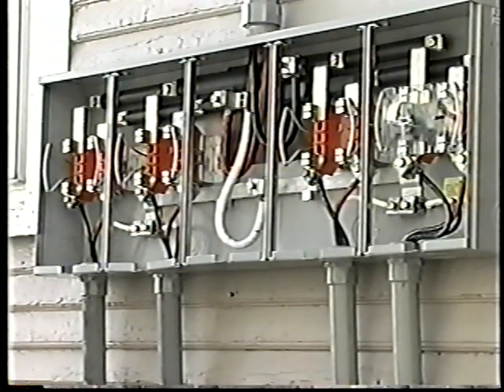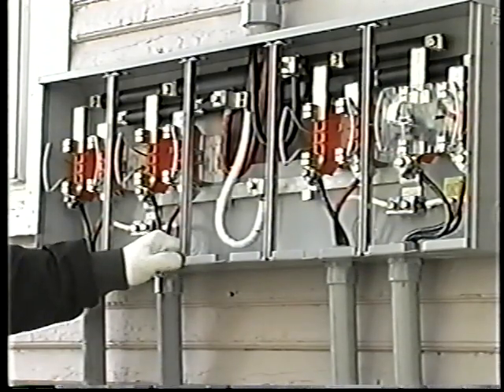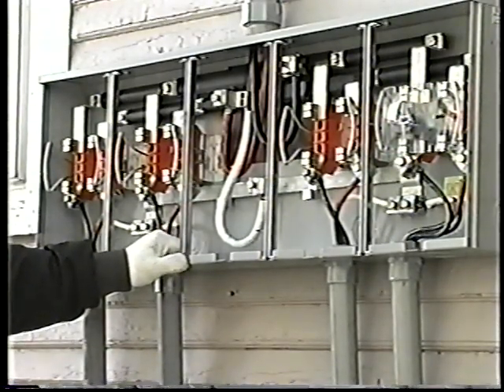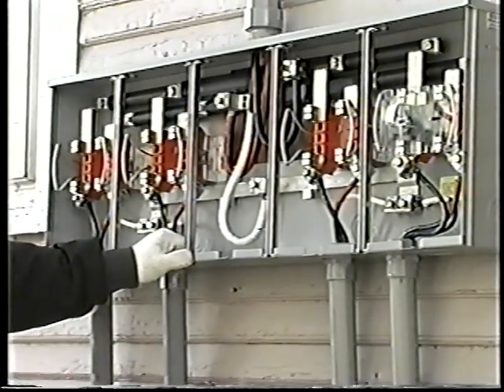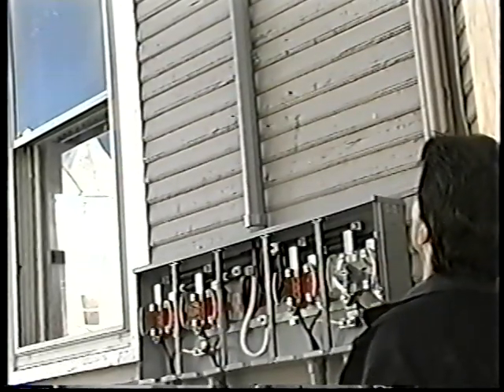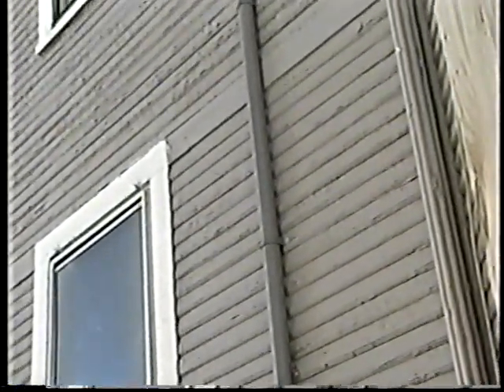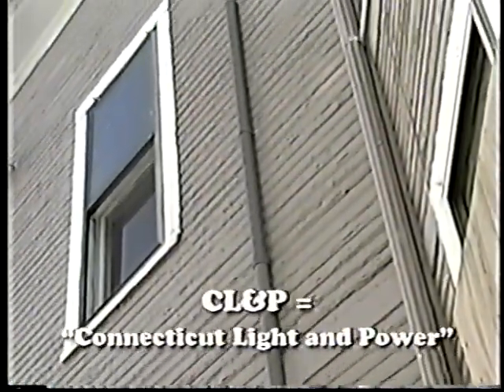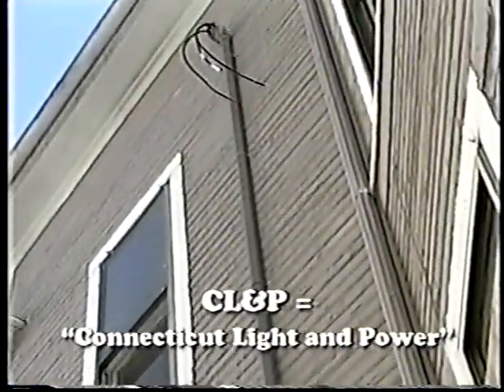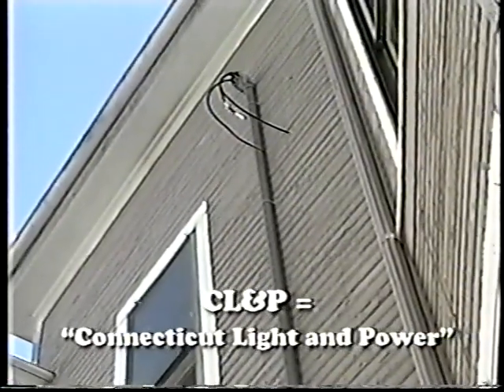Price range for a service like this one was roughly around $3,500 compared to a single family, which is right around $1,200. All services have to be in electrical conduit now. If you follow the pipe all the way to the top, you're going to have a weather head, which keeps the water from coming down into the electrical enclosures. Each wire comes out of an individual opening, and CL&P requires you to leave roughly 3 feet hanging out the top so they can connect from the street.